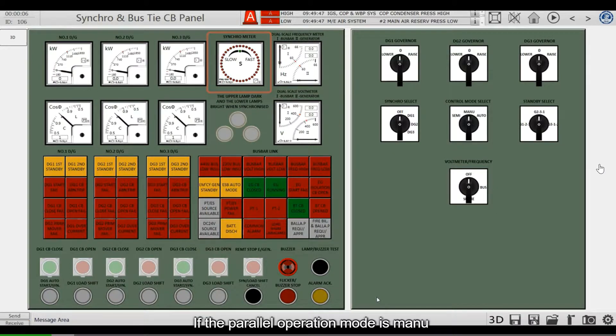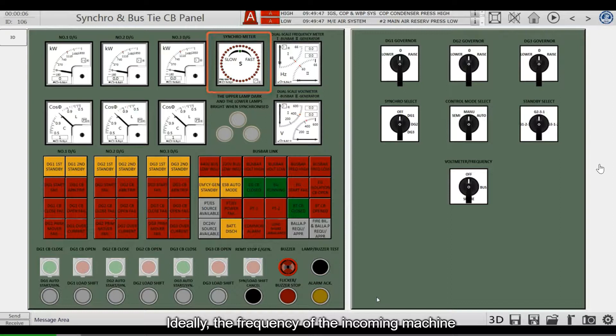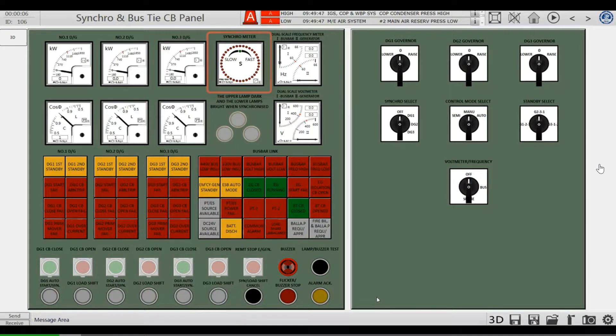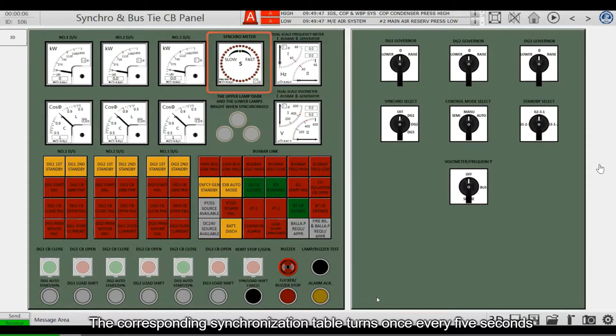If the parallel operation mode is in manual, ideally the frequency of the incoming machine is about 0.1 Hz higher than the frequency of the power grid. The corresponding synchronization table turns once every 5 seconds.